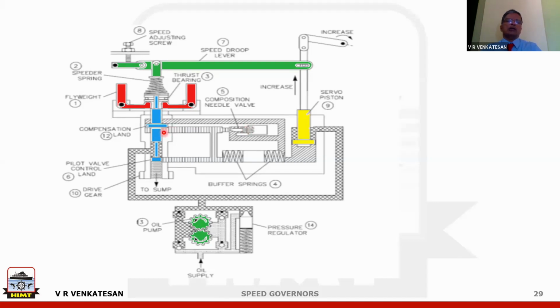So normally this has to be adjusted on board the vessel according to the engine, or after doing maintenance to the governor. All these times you have to set this. So to repeat, to explain the difference between droop setting and compensation: compensation is for temporary droop, or it is to control the amount of hunting that takes place. Droop is for controlling the permanent values, the permanent change in setting.